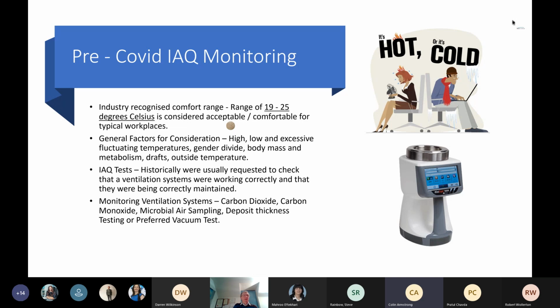But I can understand why people use it. We've also been asked to monitor carbon dioxide levels in the past. We all produce our fair share of CO2, and we breathe out almost a kilogram of CO2 on a daily basis. When you put a large number of people in a workplace, that can rise significantly, and it is typically the most relevant test parameter with regards to indoor air quality. If you know the size of the room, and you know roughly the average that a person gives off, and what your ventilation system is working at, you can roughly work out how many people should be in that room. However, with the CO2 levels, you might be asked to go in and do it in a room where there's no one in at that time, and it can change. You could have 10 people in the room one day, and 20 people the next day. So all you can do is give your opinion of what it should be.